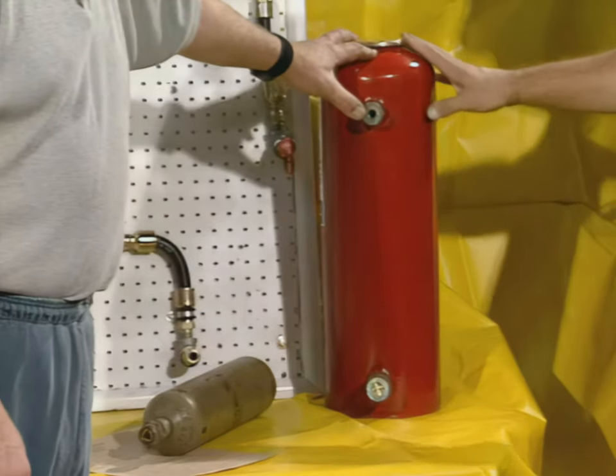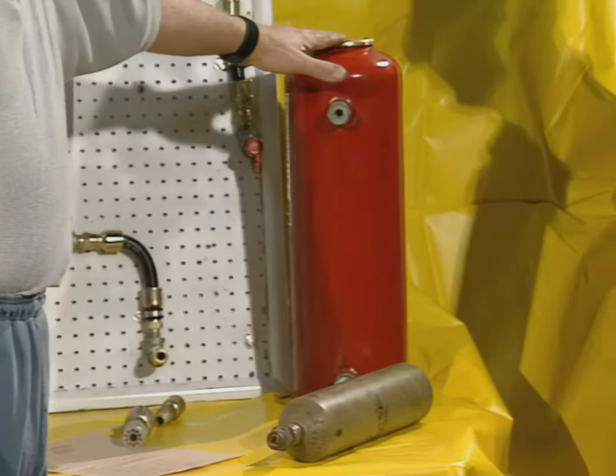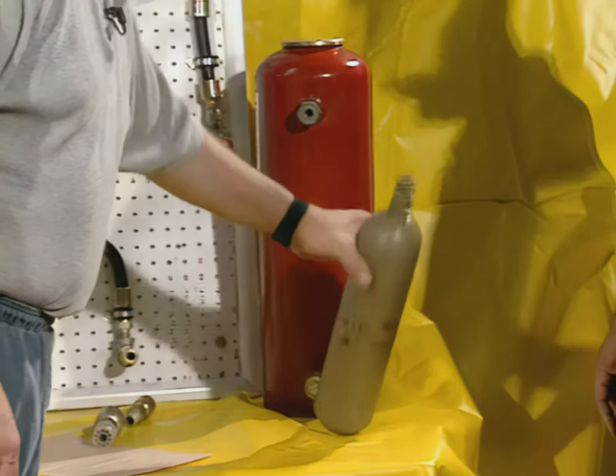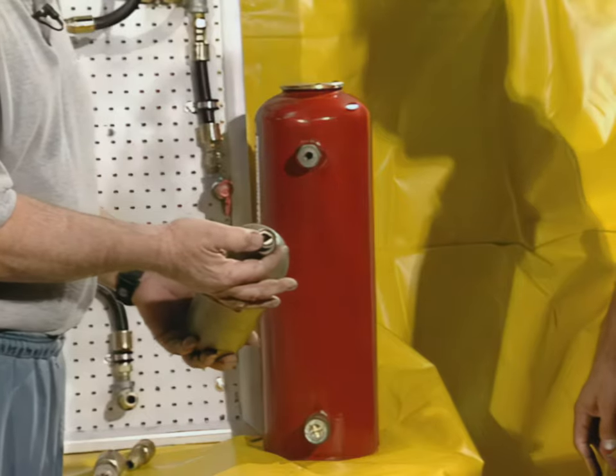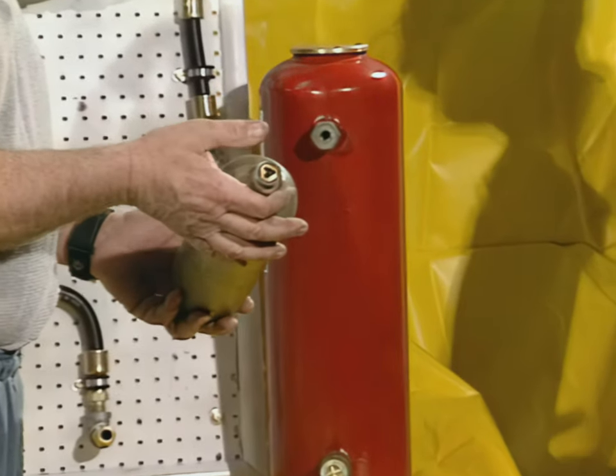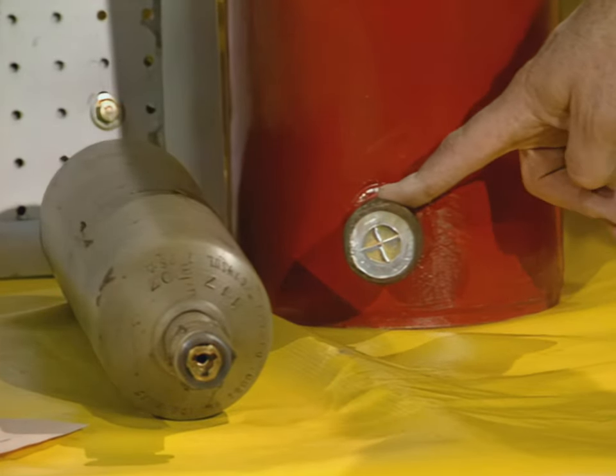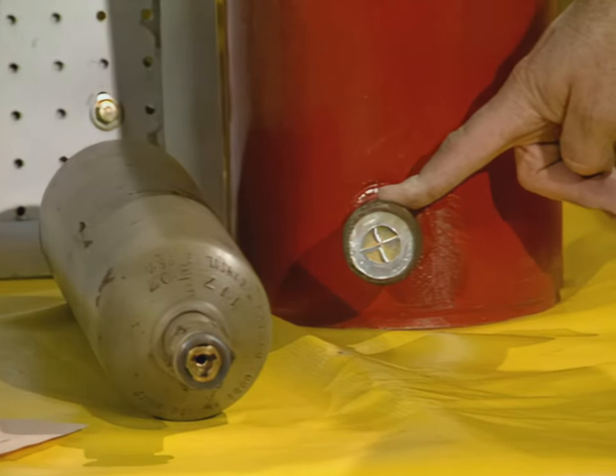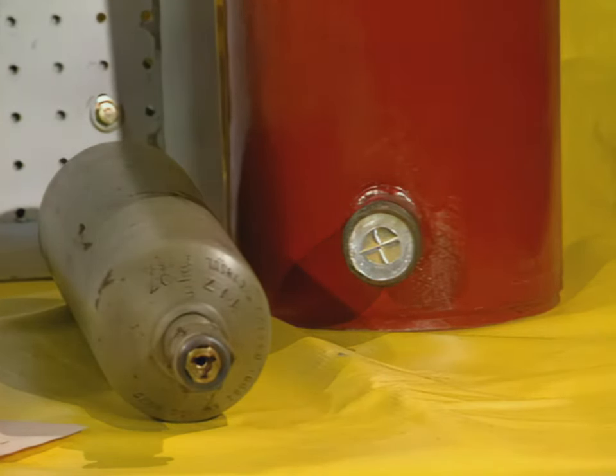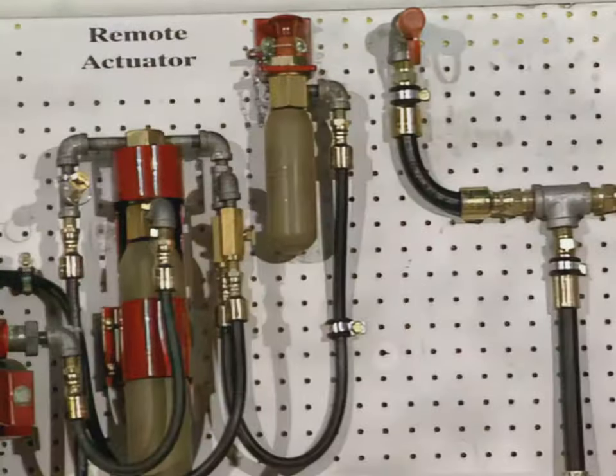This tank here is a low-temperature tank fired with nitrogen. It's also a 30-pound tank — the largest individual tank in the Ansul system you're going to find on mine equipment. This cartridge fires that one; same configuration as the CO2 cartridge, except this carries 1,800 PSI. Regarding the bursting disc, you can't put it in backwards or it won't rupture. Looking at the bursting disc on the tank, you can see the X on the face of it — that's the way it goes in.